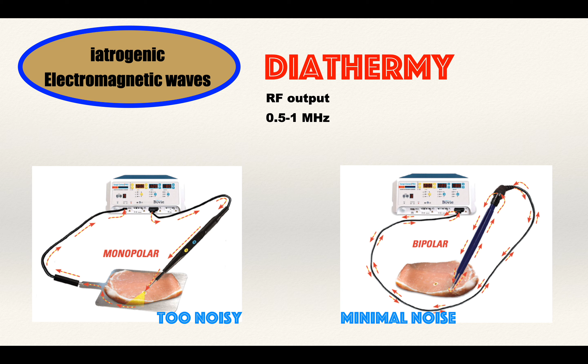It is used if surgery is less than 15 cm from the can, provided no direct hit nor fulguration is attempted, where electromagnetic waves could drag the pacemaker through the air. In everyday life, patients with a pacemaker will construct a balance between their heart, their electronic device, and any noisy electromagnetic interference. In theater, this balance should be at its maximum because of added surgical stress and identified iatrogenic noise. The anesthetist is guaranteeing this balance.